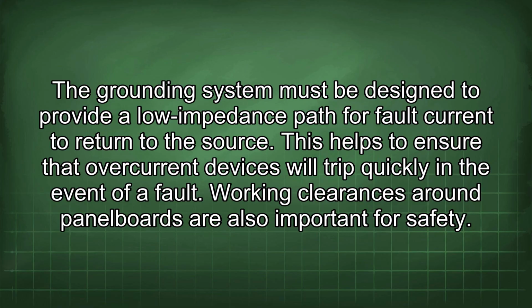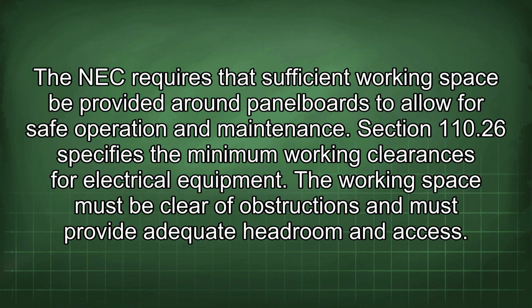Working clearances around panel boards are also important for safety. The NEC requires that sufficient working space be provided around panel boards to allow for safe operation and maintenance. Section 110.26 specifies the minimum working clearances for electrical equipment. The working space must be clear of obstructions and must provide adequate headroom and access.